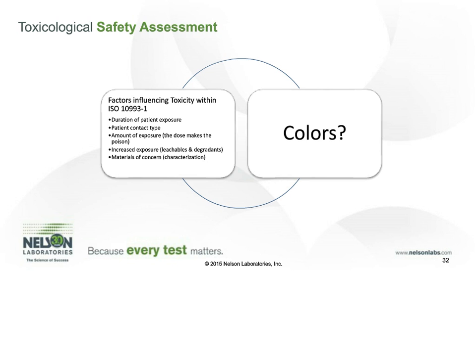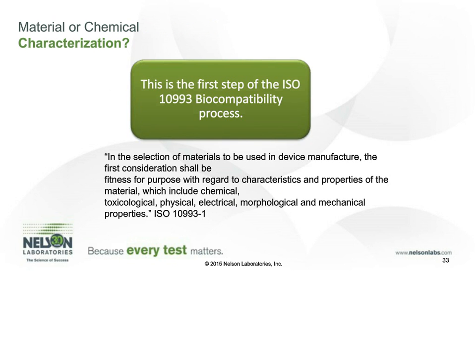So, the difference between material and chemical characterization. This is the first step of biocompatibility. I showed you the flowchart, which is material and/or chemical characterization. Material characterization goes into much more than just the chemistry. It goes into the history of the materials, the geometry, like I mentioned, the sterilization procedures, where it's being used, and other endpoints that we examine.